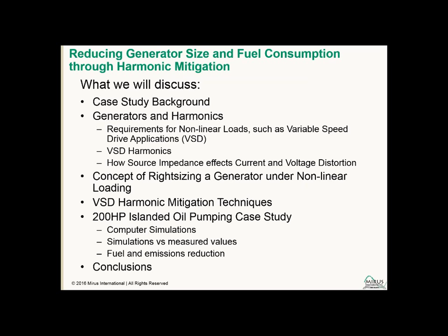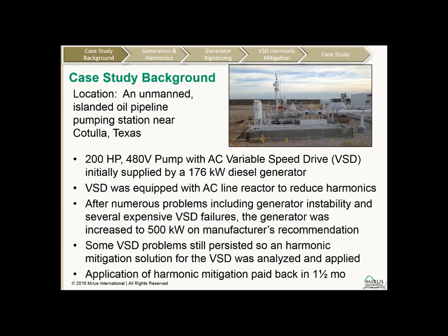So the project in question was an unmanned islanded oil pumping application on a pipeline near Cotulla, Texas. It's a 200 horsepower 480 volt pump that was supplied by a variable speed drive, and initially they had installed a 176 kilowatt diesel generator. There was no utility connection on this site. So they initially sized the generator basically 1-to-1 to the kilowatt ratings of the pump.